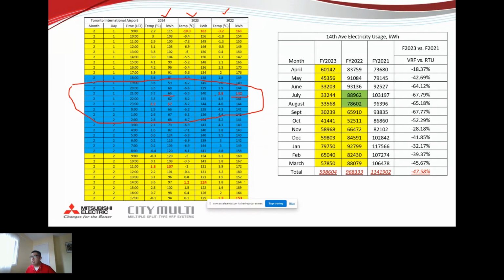During the daytime it's hard to say, because sometimes we have guests, sometimes equipment turned on, but you can see at 1.3 degrees C outside, 107, 124, and 153. Daytime has people coming in and out a lot, so it's hard to make that justification or comparison. But if you look at minus 6.3, 3.3, and 3.3 degrees C, that gives a pretty good idea, accounting for all the lights. Yes, we do publish a performance curve in heating mode as well.